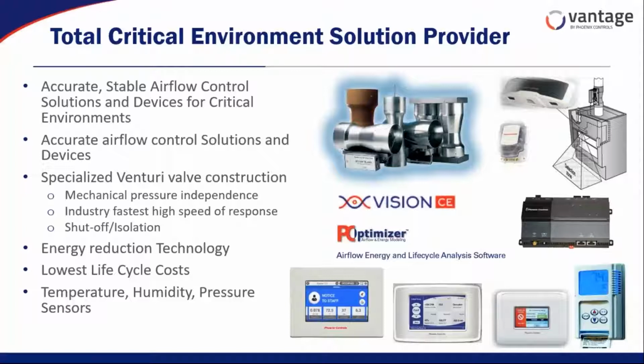When you think about a wet chemistry environment, obviously things that control fume hood themselves. So you'll have a fume hood display, you'll have sash sensors, what we call a zone presence sensor for energy setback, as well as pressure monitoring to be able to reset the pressure inside the ductwork. We also have a full line of integration controls in our platform that we have the PCI, which is actually integrating the room level controls into the building automation system.